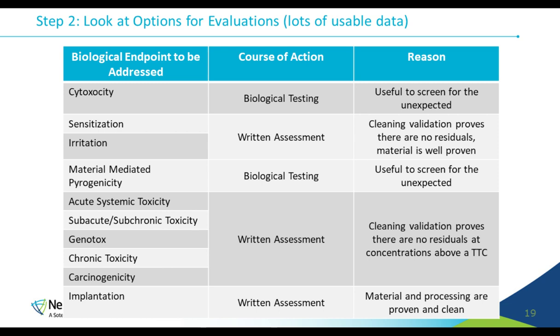Now, if we had good chemistry data, and when I say chemistry data, I mean data that supports that the device is very clean from a chemistry perspective. So if they had history of running TOC, total organic carbon, and total hydrocarbon content as part of their cleaning validations, and it was very clean, then we can leverage that along with the history of safe use of the material to avoid almost all of the testing.